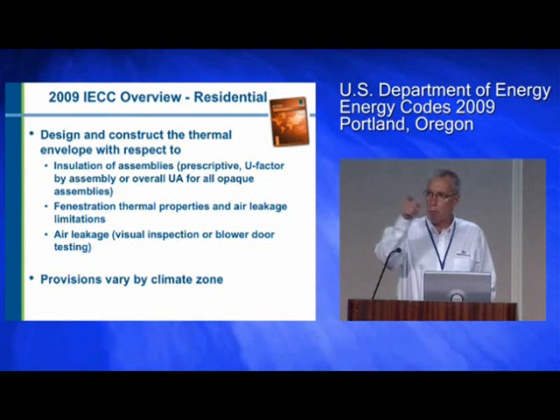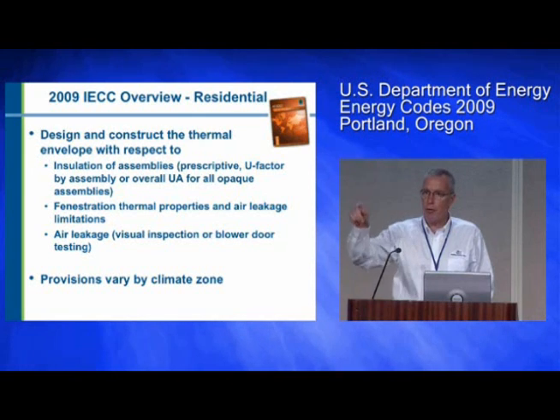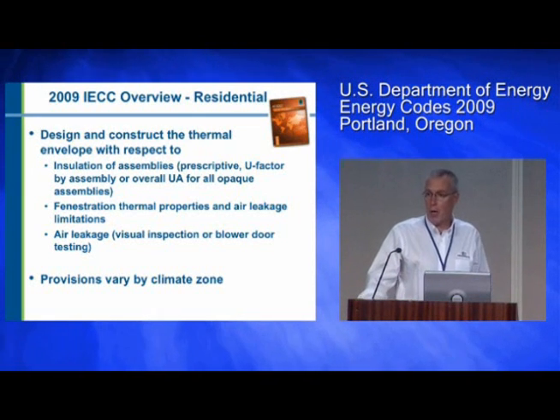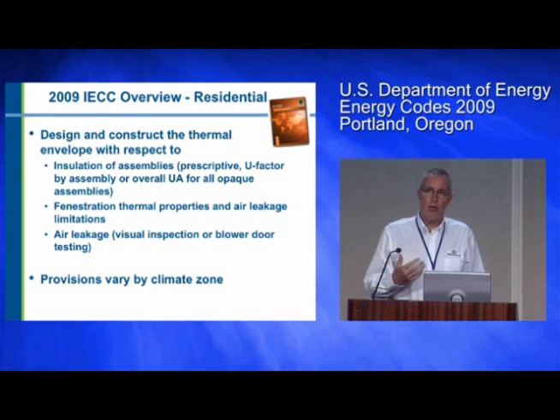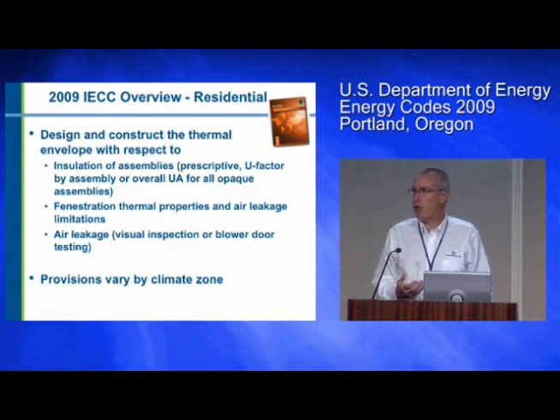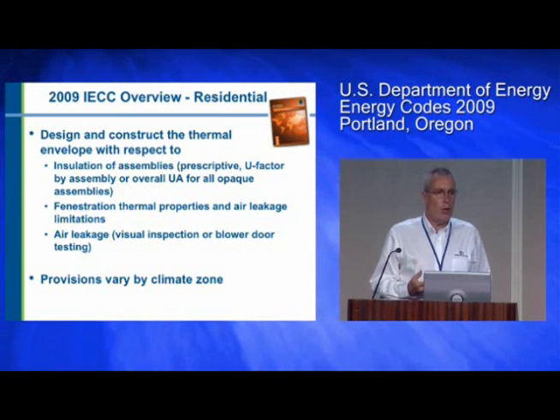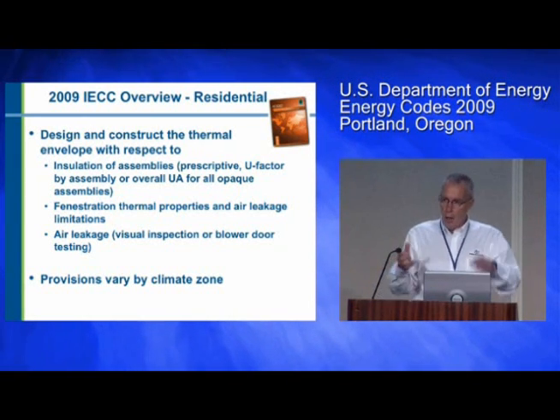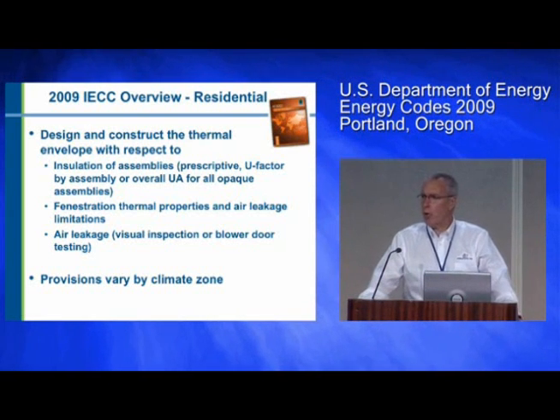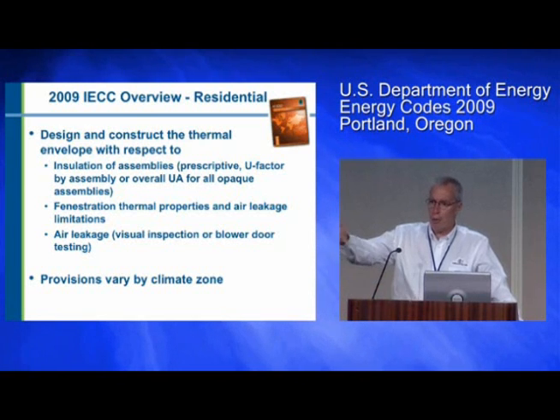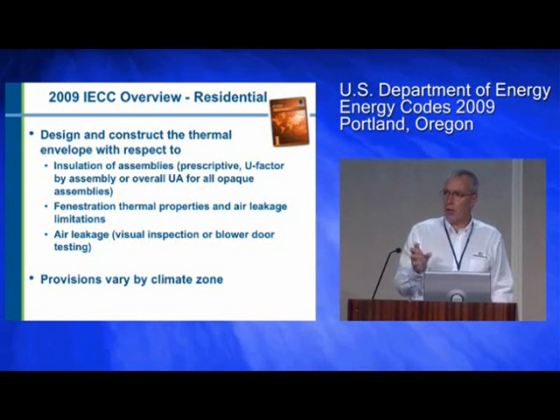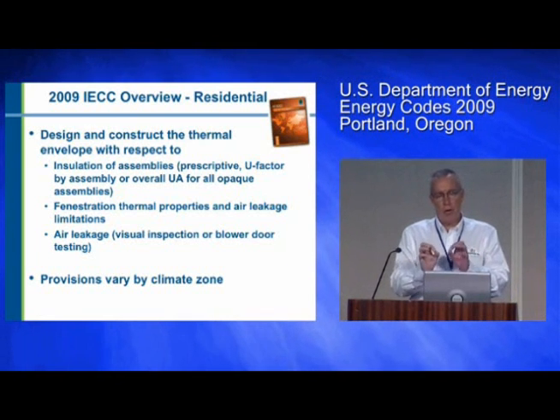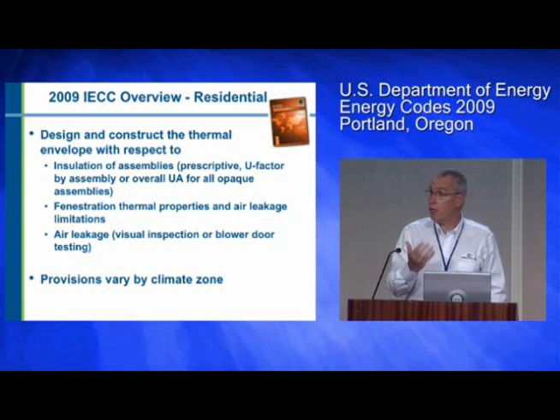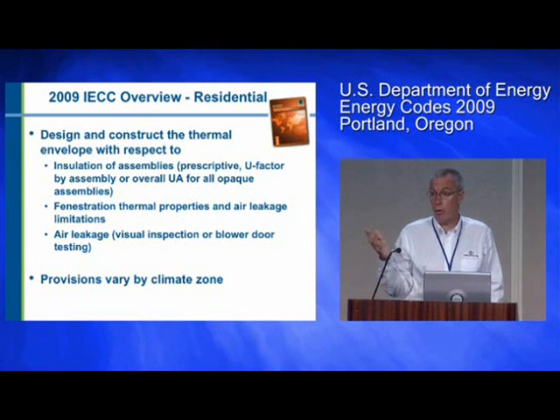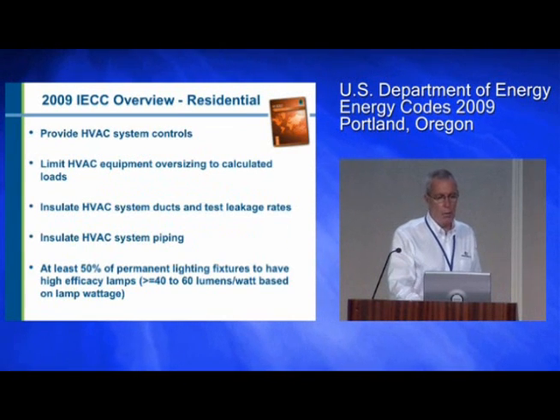Again, historically, if you remember the original ASHRAE standard, it had a graph of U values for assemblies by heating degree day. And over time, what's occurred is, in the county where I live, Fairfax County, Virginia, under the statewide mini-maxi code, heating degree days go from 3,950 to 5,002. It's really hard when the municipality is a county that's fairly large. It's really hard to say, well, on this side of the street we're going to do this number, and on that side of the street we're going to do another. So over time, things have gravitated toward less specificity and gone into climate zones to make it a lot easier. So in Virginia, we have one zone. We're in Zone 4. It's real easy throughout the state to deal with.